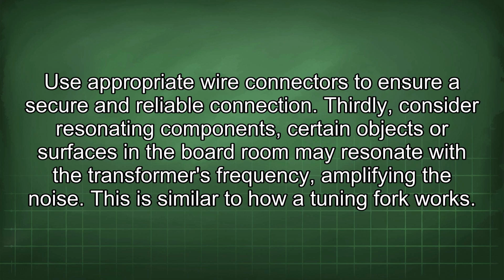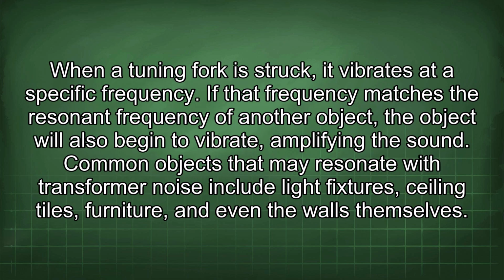Thirdly, consider resonating components. Certain objects or surfaces in the boardroom may resonate with the transformer's frequency, amplifying the noise. This is similar to how a tuning fork works. When a tuning fork is struck, it vibrates at a specific frequency. If that frequency matches the resonant frequency of another object, the object will also begin to vibrate, amplifying the sound. Common objects that may resonate with transformer noise include light fixtures, ceiling tiles, furniture, and even the walls themselves.